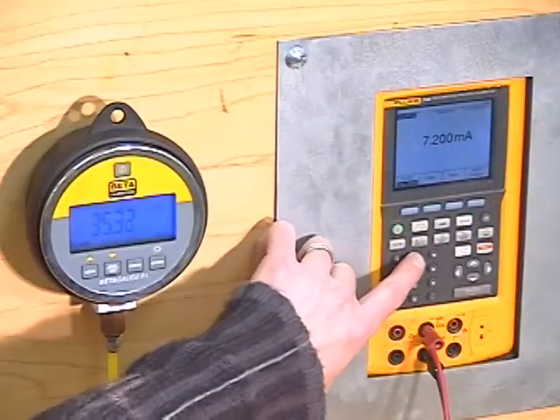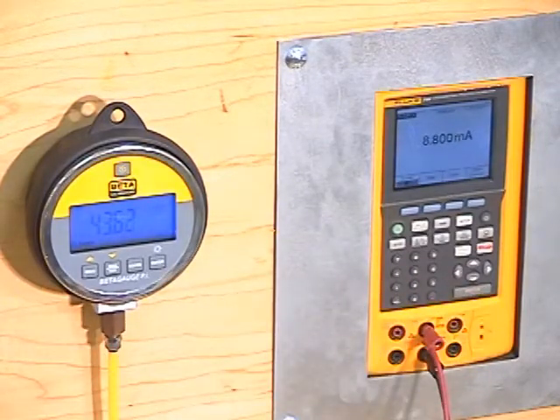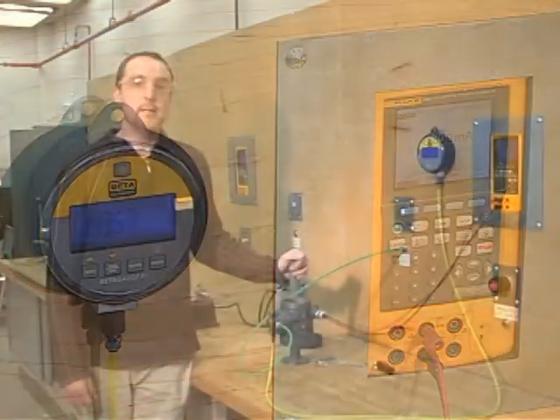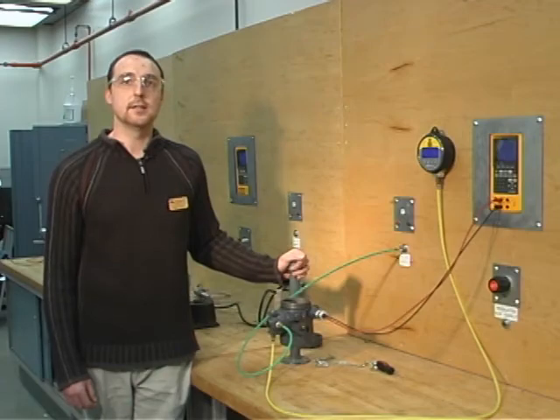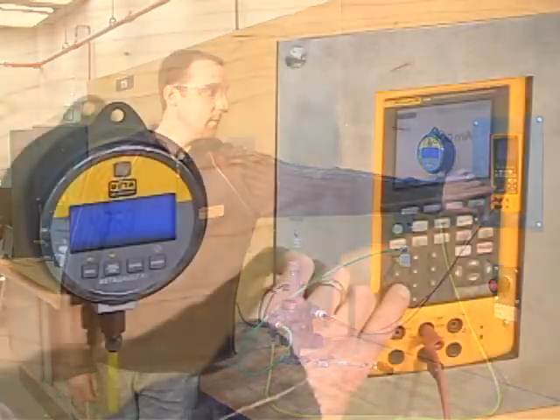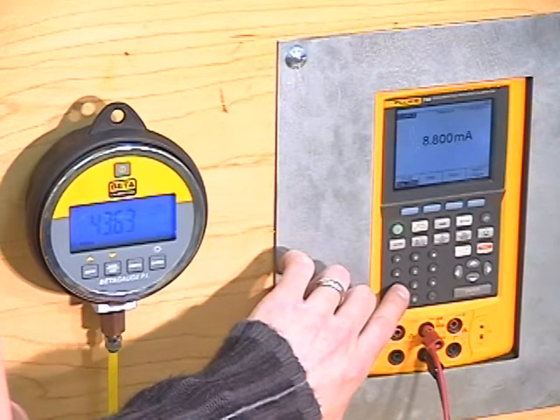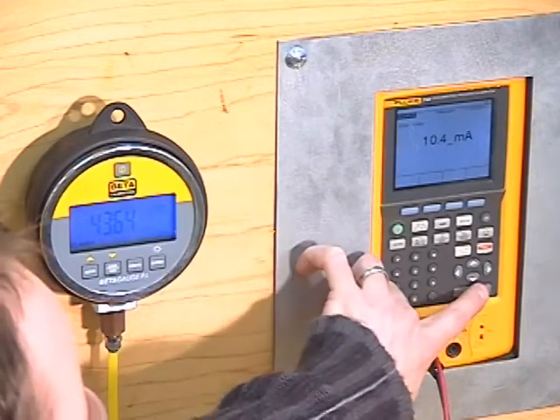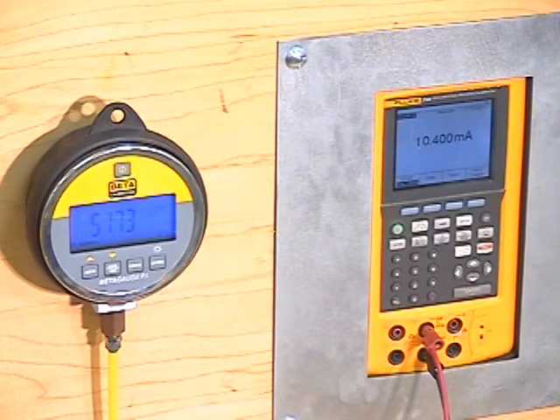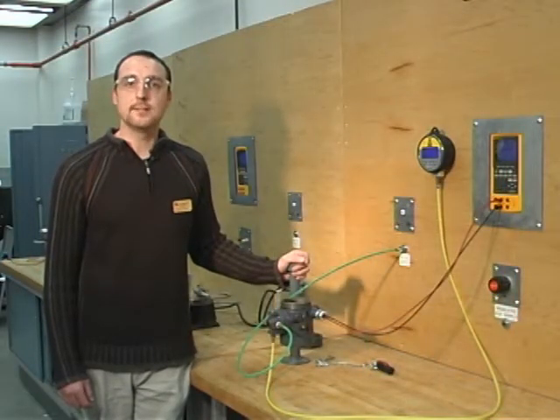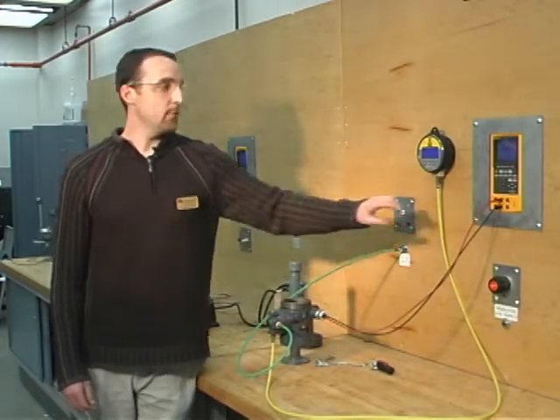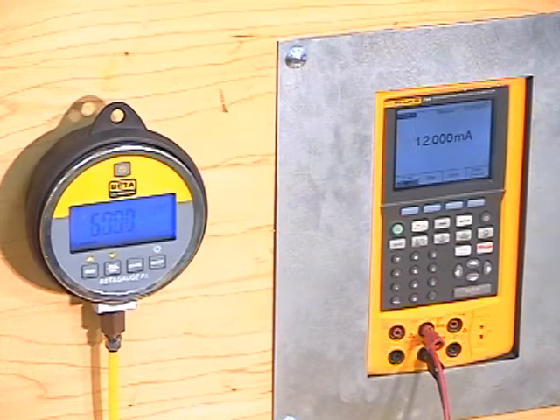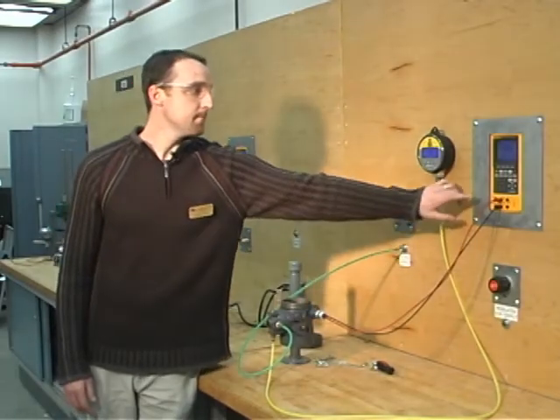Next, let's go up to 8.8. At 8.8 milliamps, we are at 43.57 kilopascals. Next, we'll go up to 10.4. At 10.4, we are reading 51.73 kilopascals. Next, for a halfway point at 12 milliamps, we should be rendering around 60 kilopascals, and currently we are at 59.95 kilopascals. At 13.6 will be our next step.